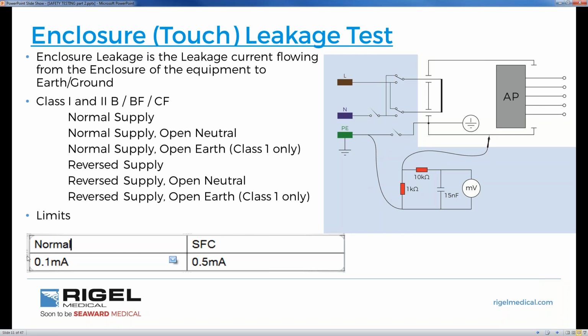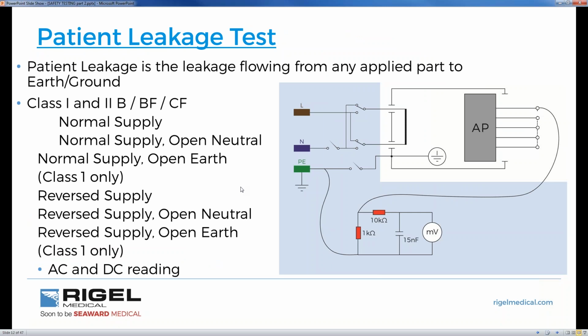And here are our pass-fail limits. The pass-fail limits of 60601 have a correlation with the physiological effects of current, which I discussed in the first part of our presentation. Patient leakage tests. So we've discussed earth leakage and we've discussed enclosure leakage. The patient leakage test is the amount of current that will flow from an applied part through our body model to the protective earth.